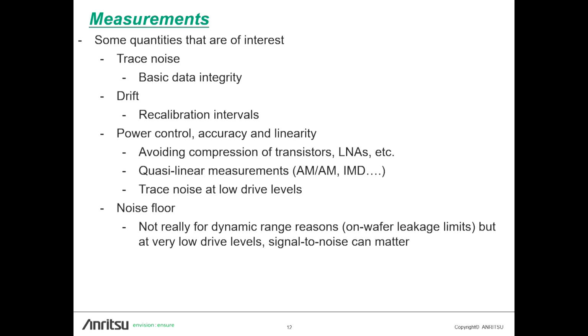And then noise floor, and again, one typically isn't going to be measuring a high rejection filter or something over these kind of bandwidths. But if you are testing a device that needs a very low drive level to avoid compression, say minus 40, minus 50 dBm, the actual noise floor does sort of matter for SNR reasons.